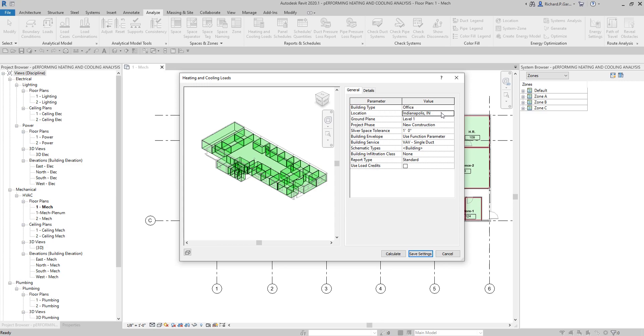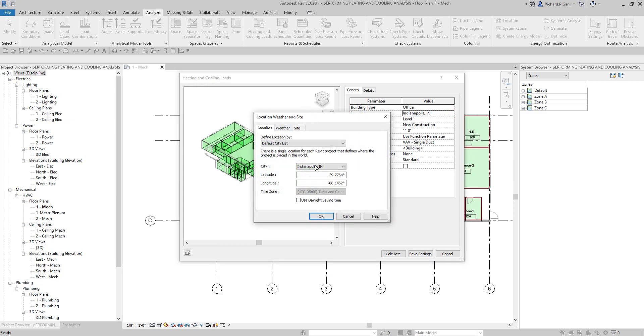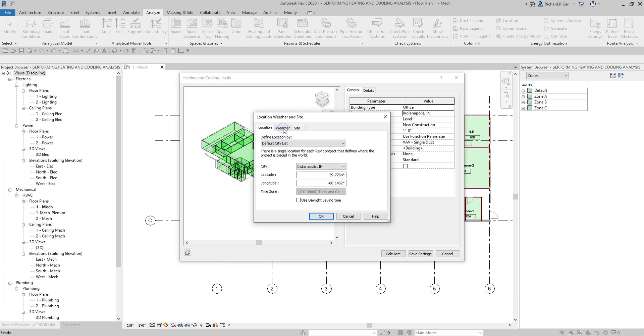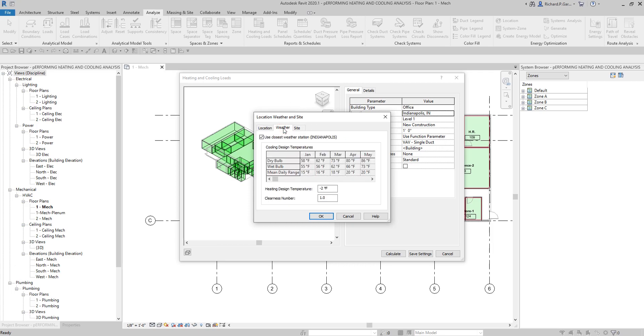For the weather, let me go to the Weather tab. Of course, you can always select the location of the project you are working on — you can select any city you want, or you can also select the Internet Mapping Service. I'll select the closest weather station, which is Indianapolis. For the heating design temperature, I'll just use the default value: minus two degrees Fahrenheit, and one for the clearness number.